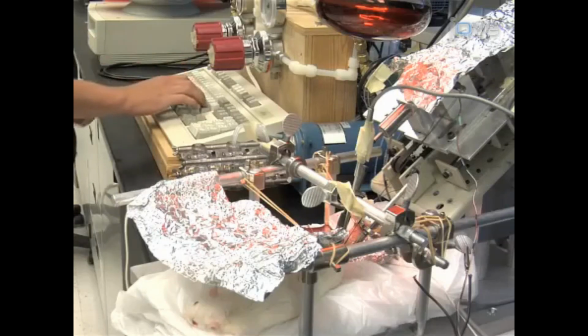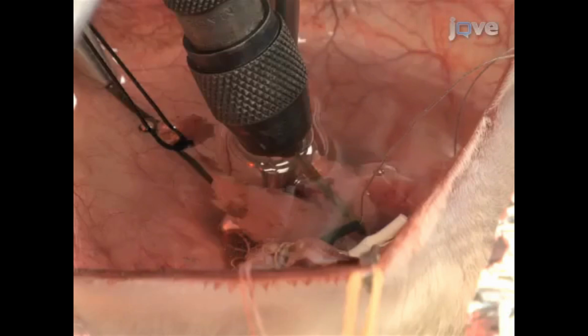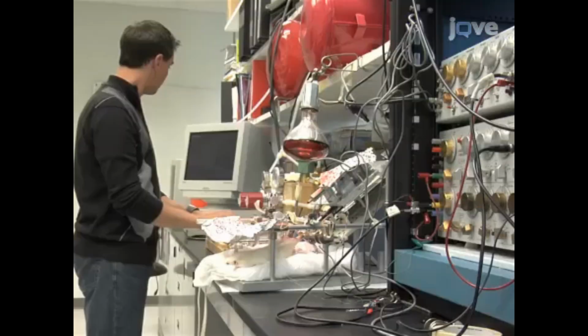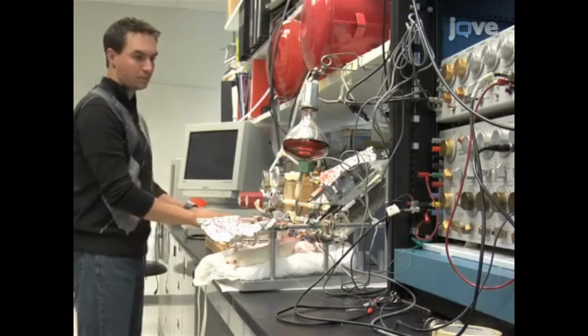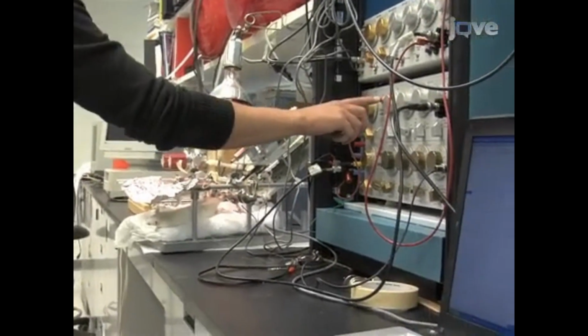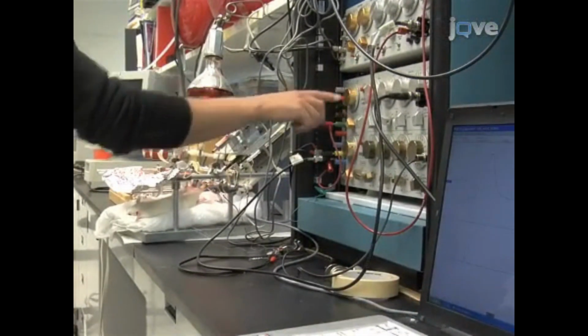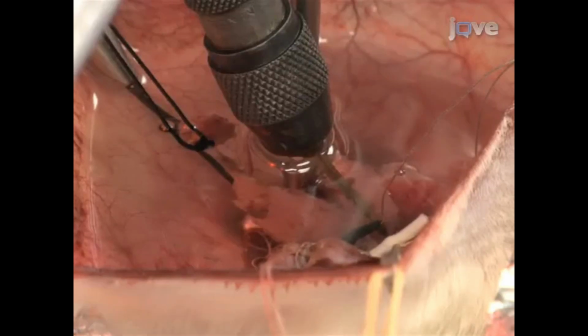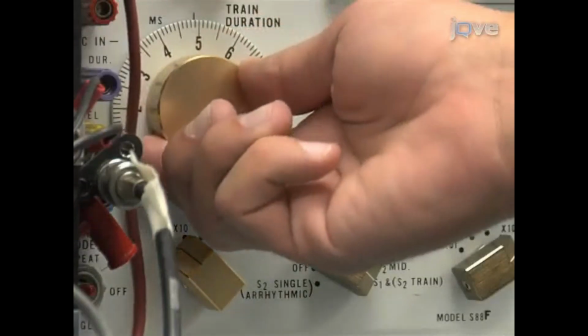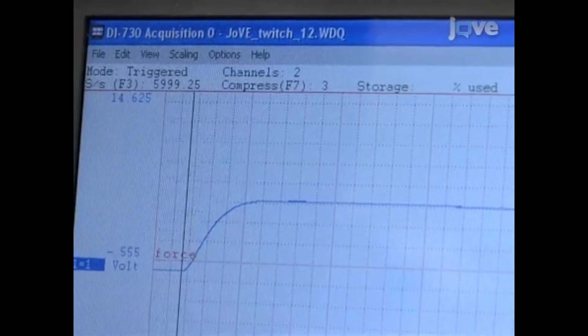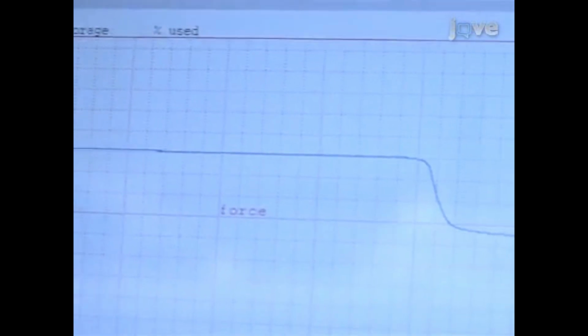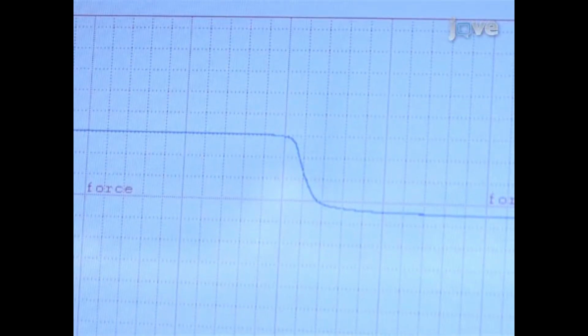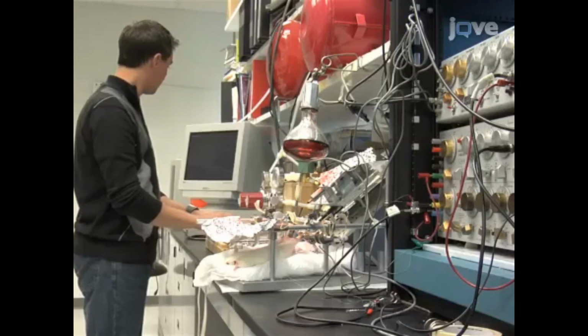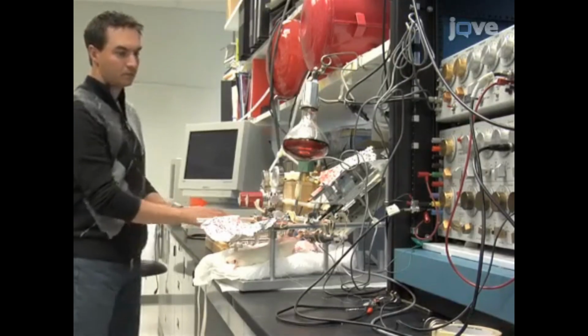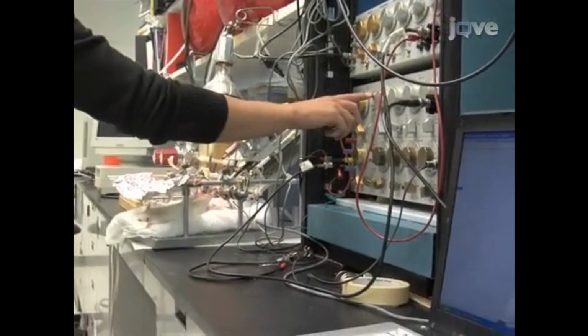Next, increase the muscle length in 1 mm increments and measure the contraction amplitude at each length. Use double pulse stimulation of 200 Hz. When the length that provides the maximum contraction amplitude is determined, set the muscle at this length. Now set the stimulator to deliver pulses at 200 Hz for 500 milliseconds to generate a completely fused tetanic contraction. This tightens all muscle connections, including the knots on the muscle. Then, redetermine the reference length, and the muscle will be ready for experimentation.